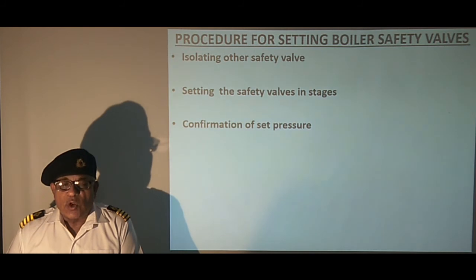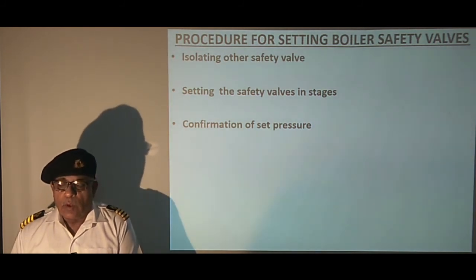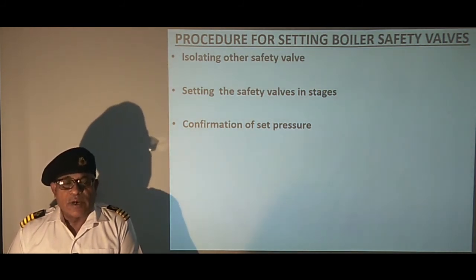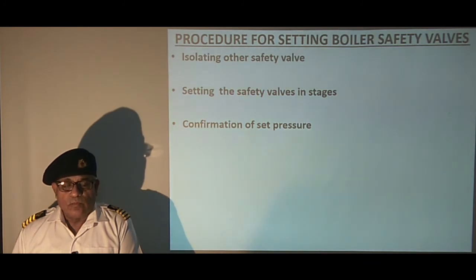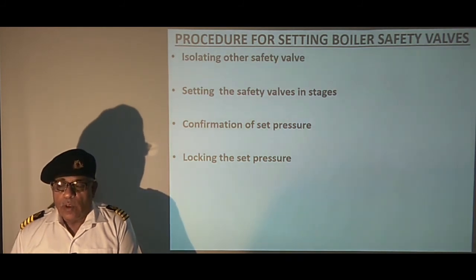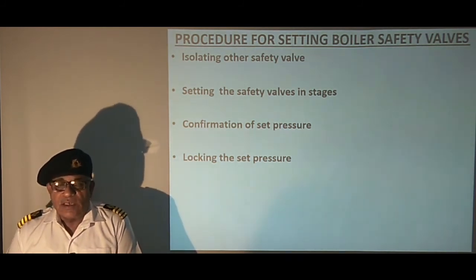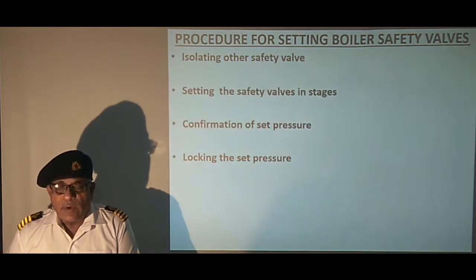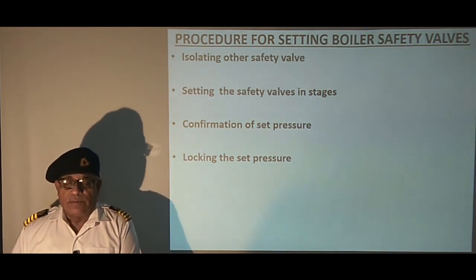Third step is confirmation of the set pressure. Raise and lower the pressure to confirm that it opens at a correct pressure. Next is to lock the set pressure. Compression ring of the correct size is fabricated and fitted in place after splitting in two parts to prevent alteration of the setting due to vibration. Additional lock nut is fitted in yoke type, full lift and consolidated type safety valves.